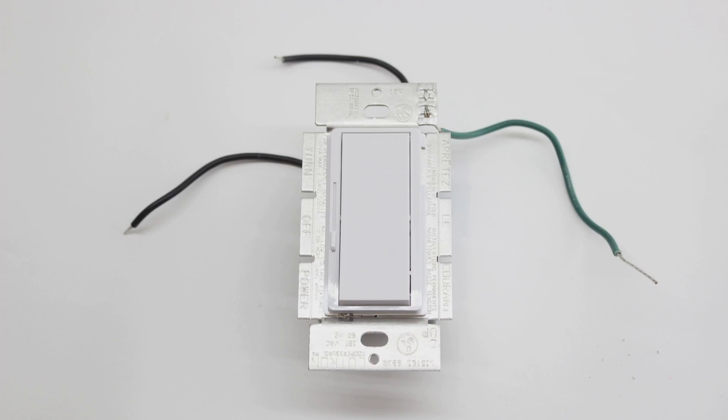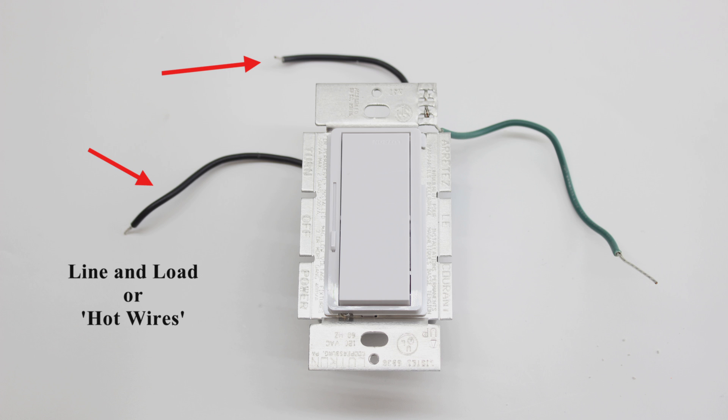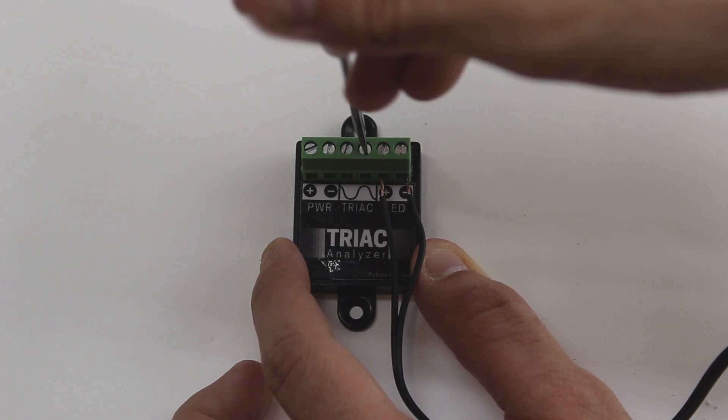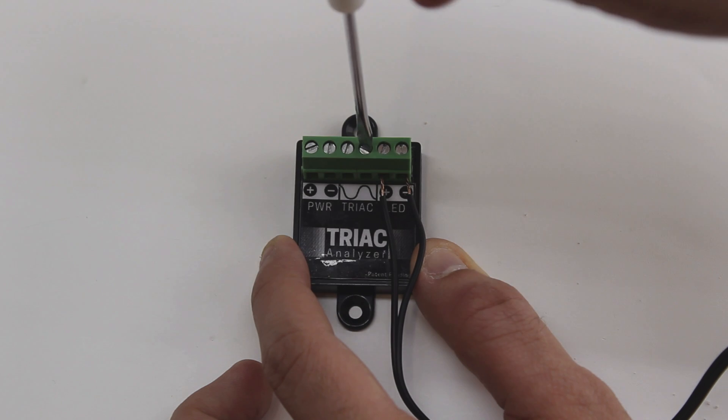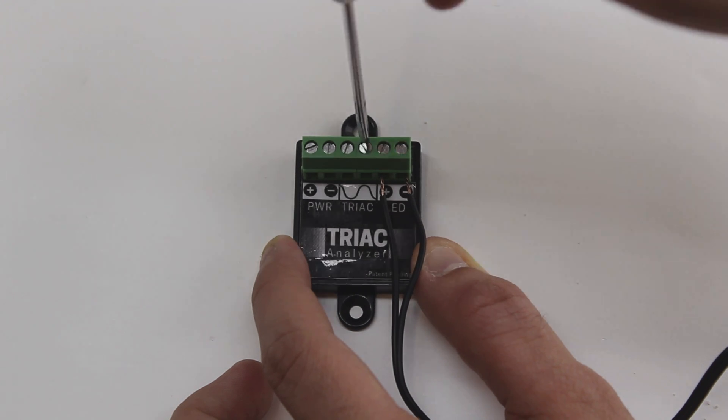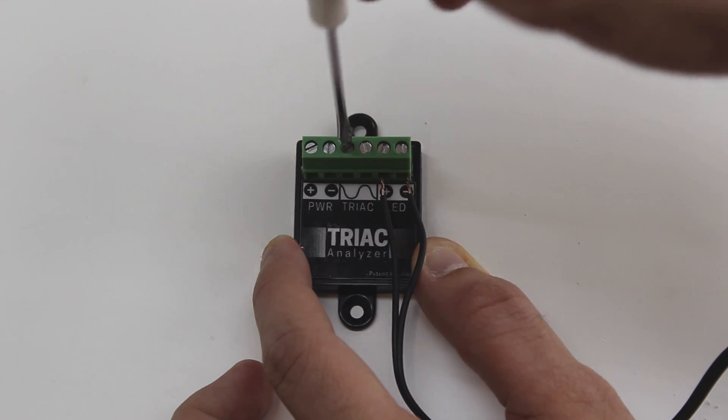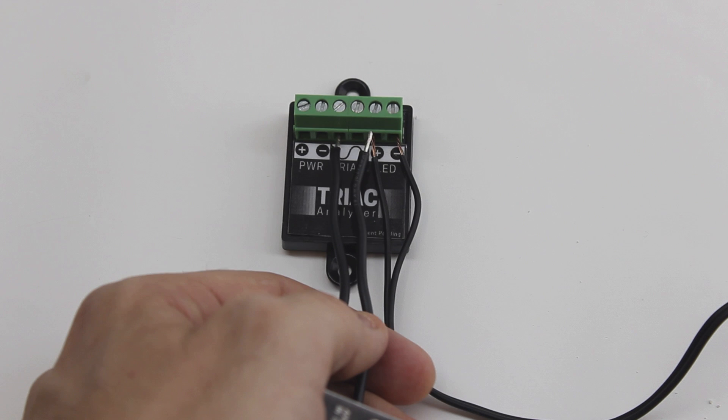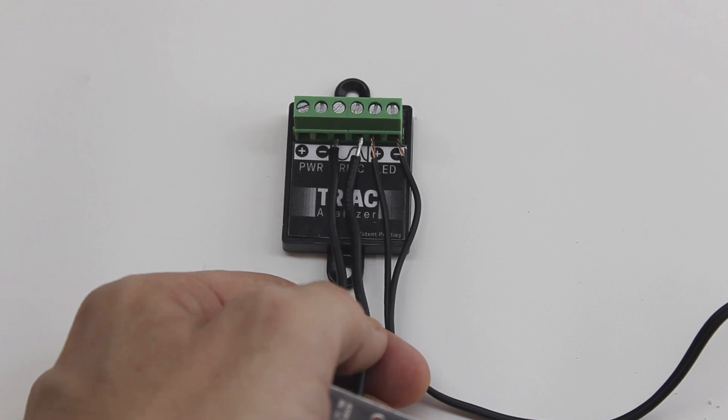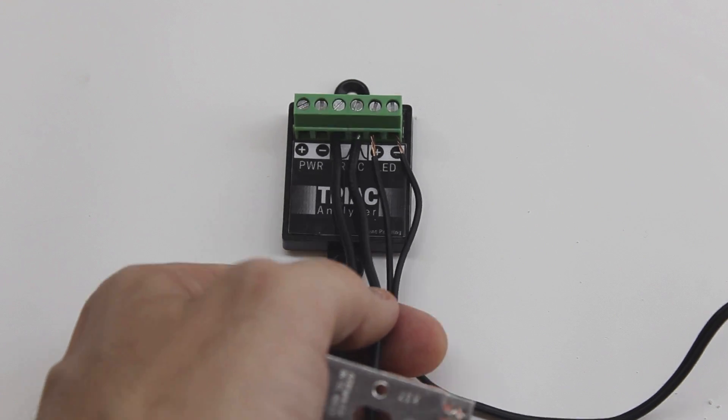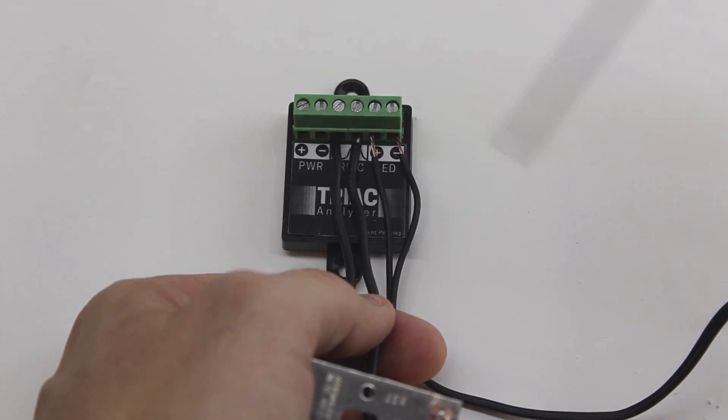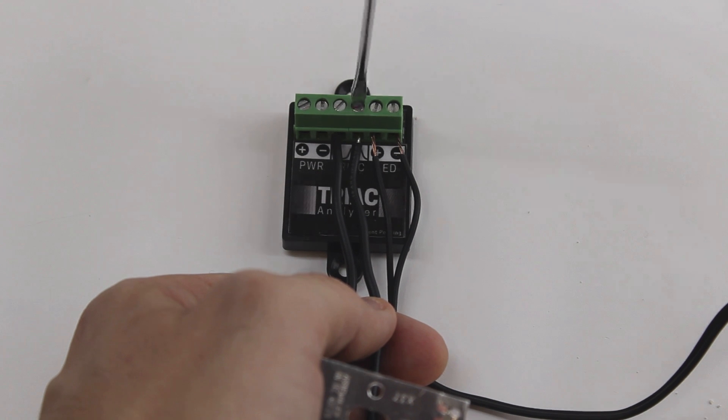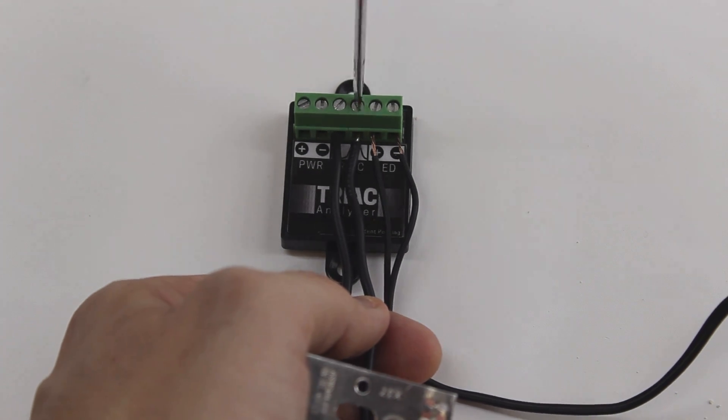We will now terminate our analog triac dimmer into the analyzer. Your dimmer will have two black wires known as the line and load or hot wires. Depending on the type of dimmer, you may find a ground wire in addition to your line and load wires. Do not worry about this wire for it will not be needed for this demonstration. Strip back the ends of both hot wires just as you did your cable. Loosen the middle screw terminals marked triac, insert your wires, and tighten the screws. These are the only wires in which you do not have to worry about matching polarity.